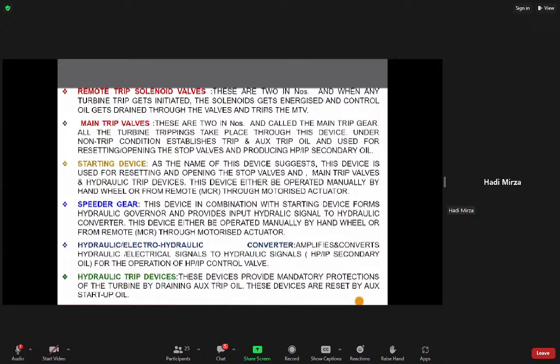These are some devices which are in the governing rack and protection rack. These are the main devices I have covered. Remote trip solenoid. There are two remote solenoids in this governing system. Basically, they are in series. These solenoids get energized and control oil gets drained through the valves and trips the MTV. Basically, when any mishap happens to the unit, any tripping is to be initiated. First, this RTS will energize and trip the port connected to control oil from trip oil. It will just change the port from control oil to drain. This is the function of RTS.